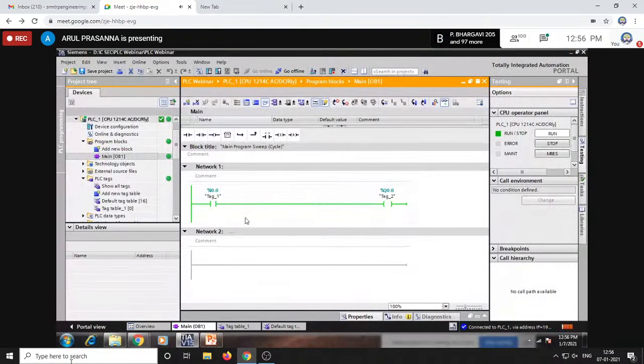So the CPU will come and check with my program. This I0.0 is directly connected to Q0.0. So what it will do is go for the PIQ chart and update the byte value of Q0.0 to 1.